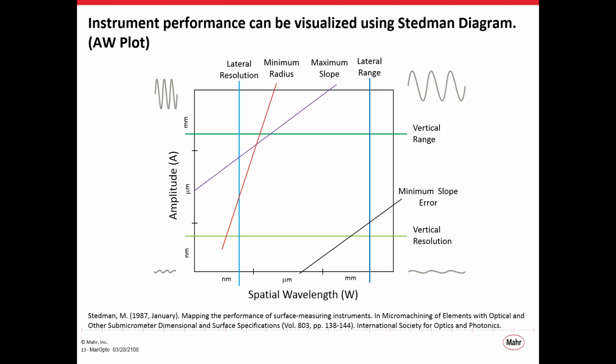But for example, for the piezo interferometers, what we're really plotting is height deviation and slope deviations, and not necessarily the absolute surface shape, because with a piezo interferometer you measure the difference from a reference. So it has to be taken with a grain of salt, but I think it's a very good way of looking at how the measurement ranges of the different instruments overlap.